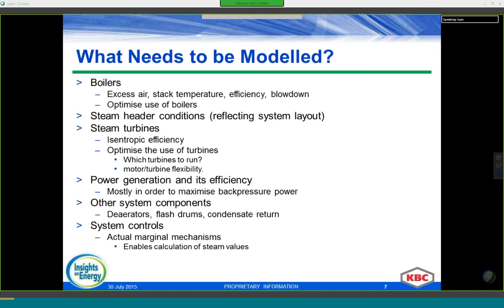Before we think about what we need to include in the model, we need to know what we're going to use the model for, so we make sure we include sufficient detail. All major components of the steam system must be accounted for in one way or another to capture the system's interactions. However, the modeling approach for each piece of equipment can be simple. For boilers, we need efficiency — we could include stack CO₂ and temperature — blowdown, steam load, and the firing duty, which is the main economic term. For headers, we need the header pressure and temperature.